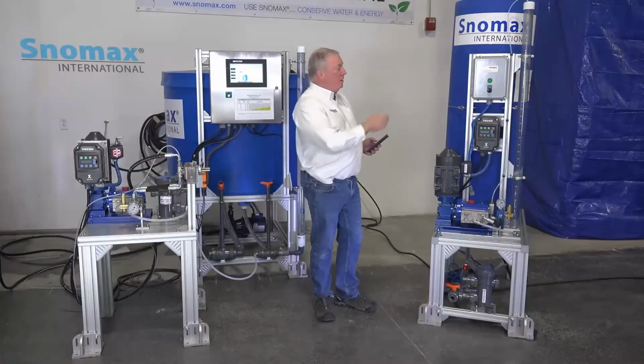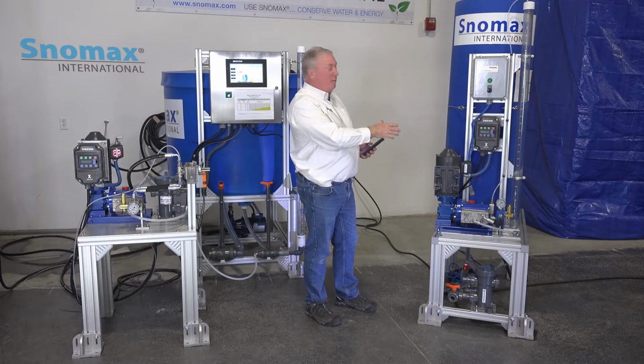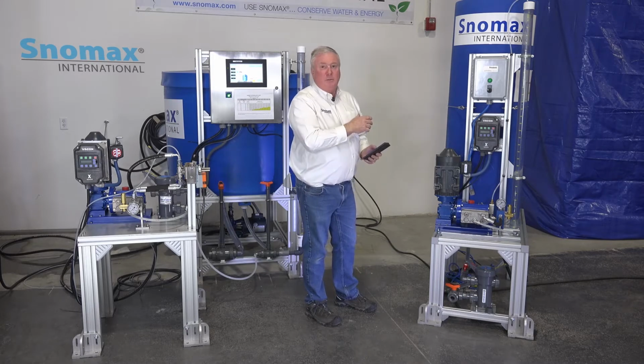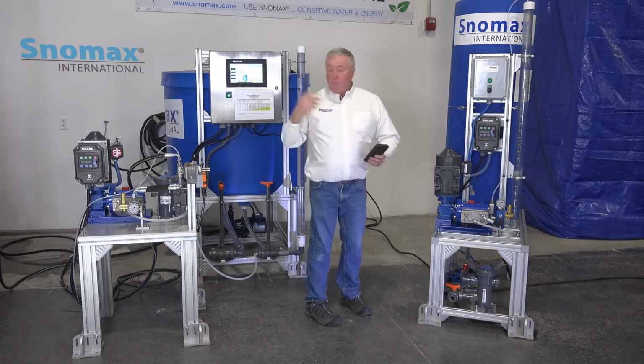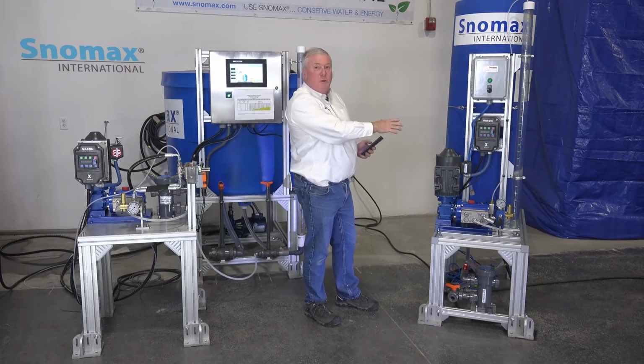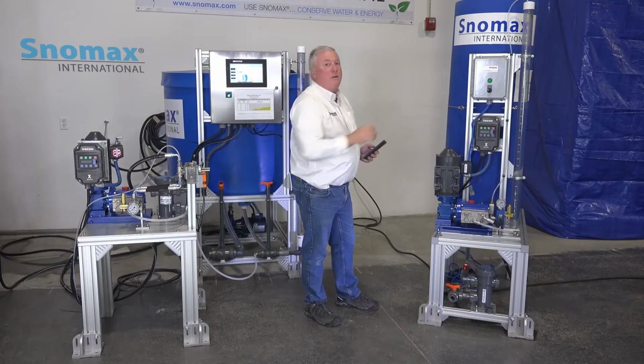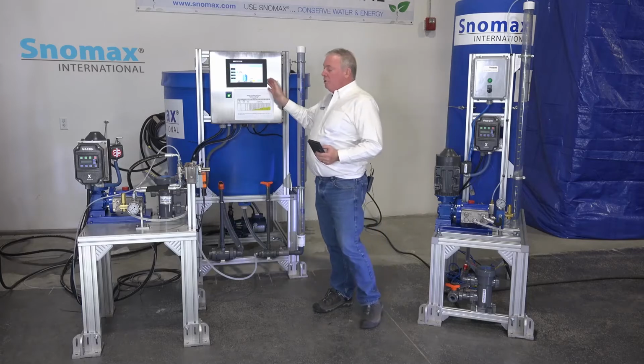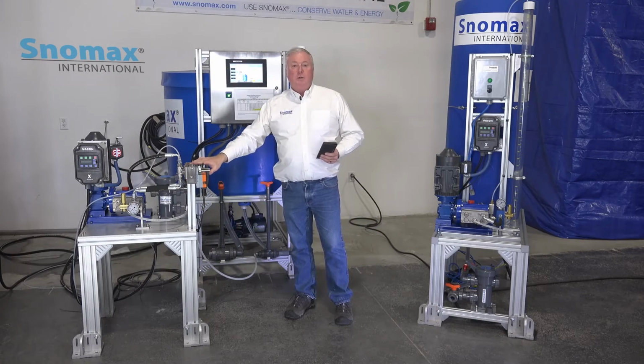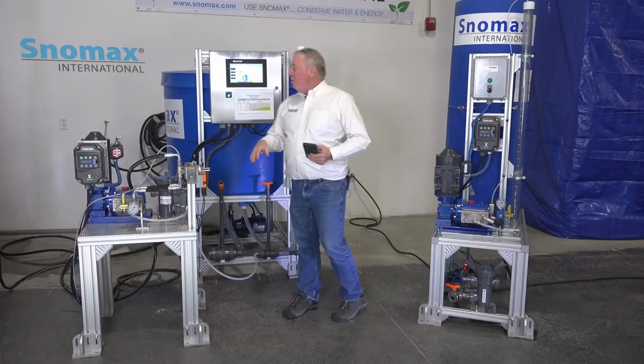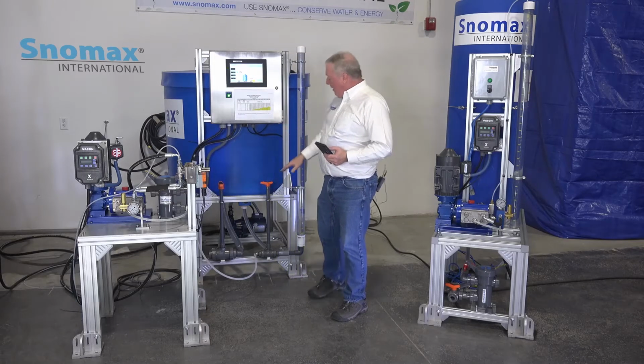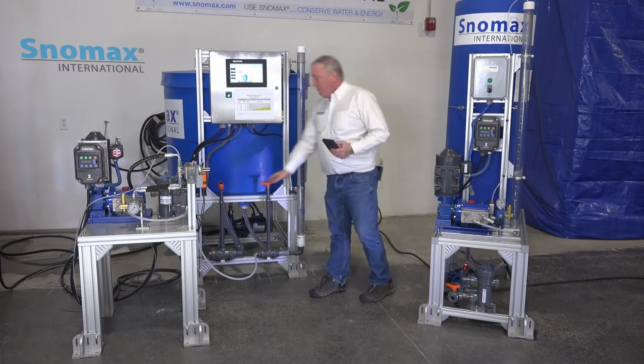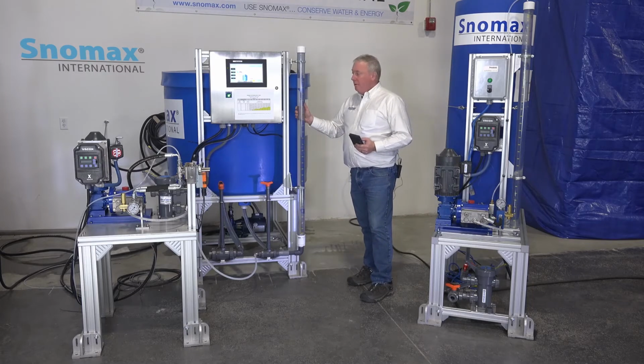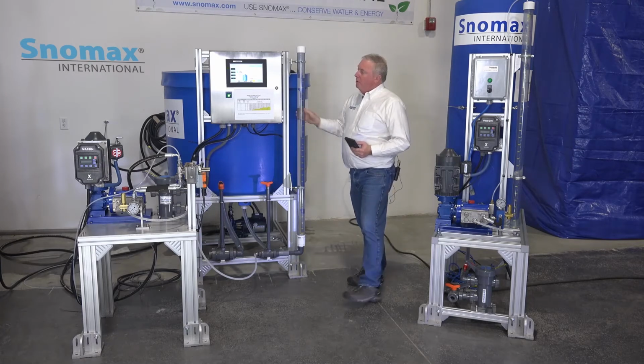We started by showing you on our smallest system how to calibrate the system. We went into the greatest level of detail on this one because if the injection system that you have at your site doesn't look exactly like one of these three, I think the principles that we showed you on this one will most closely match what we showed you here. So on this one, with our touchscreen and automated ball valves, we don't need to turn the lead valves. So all we're going to be doing in this system is interacting with the three-way valve and the calibration column.